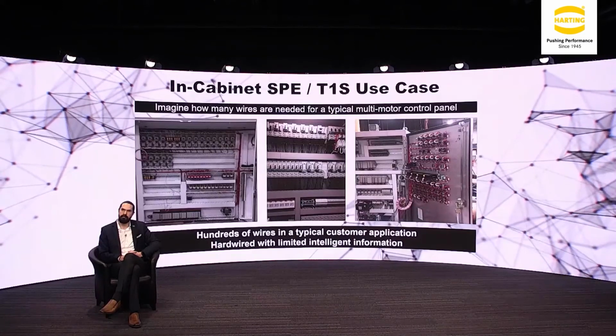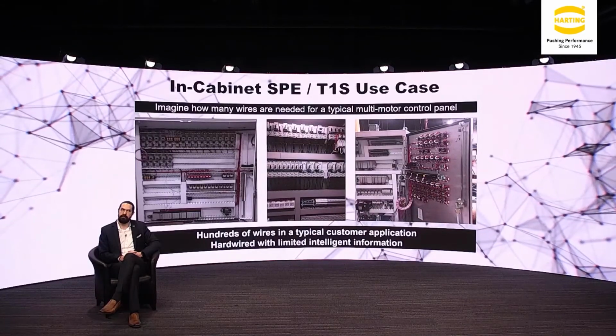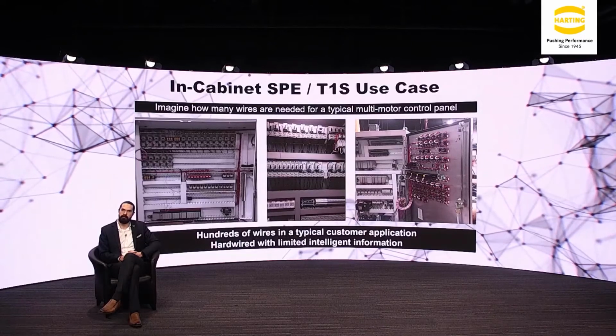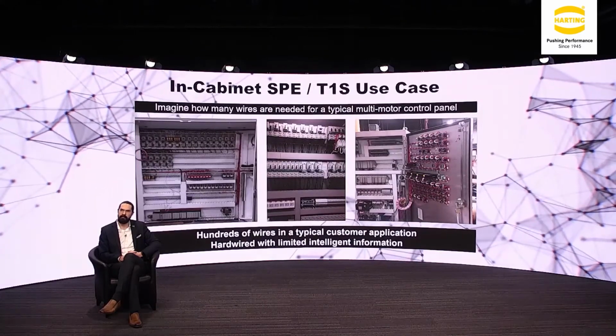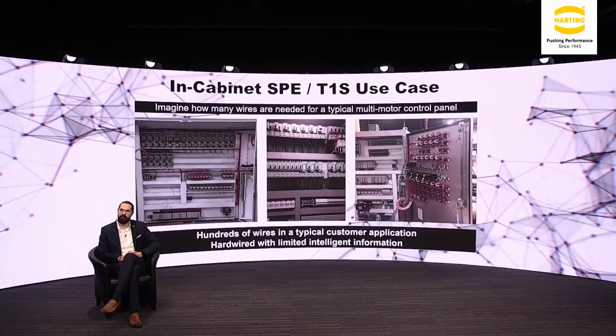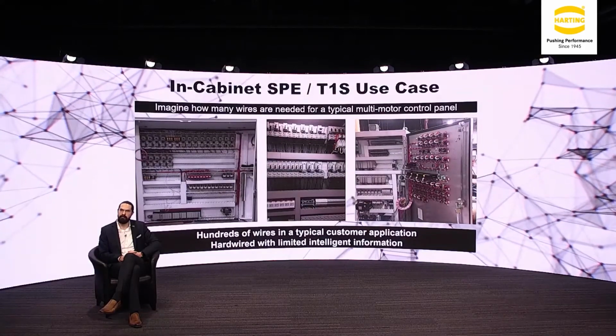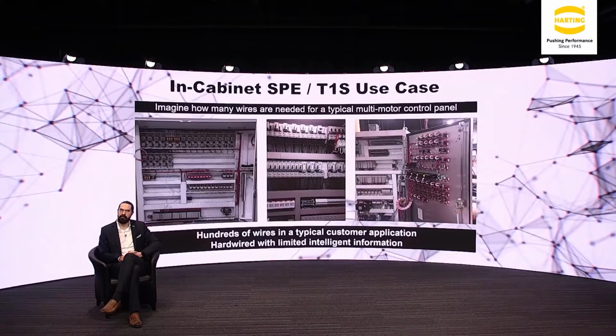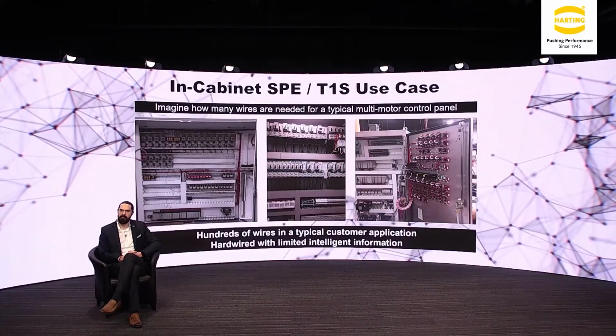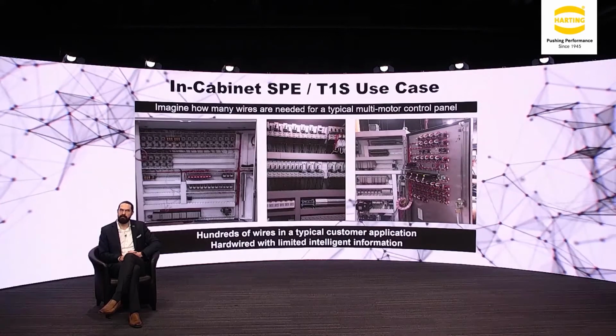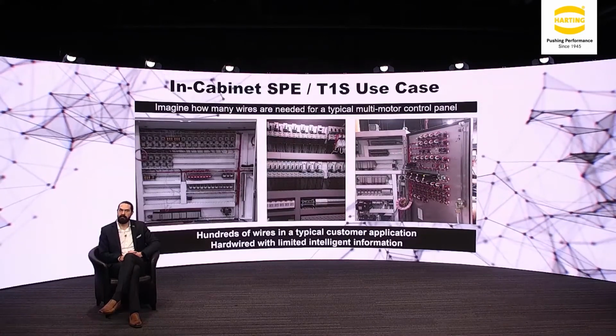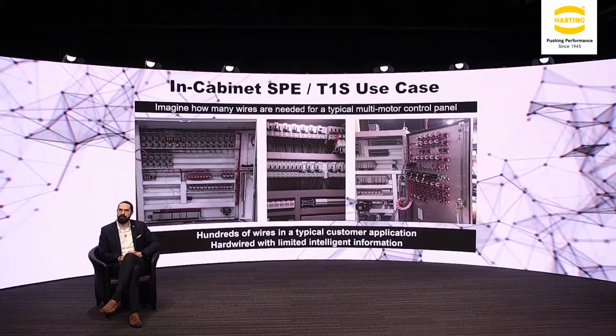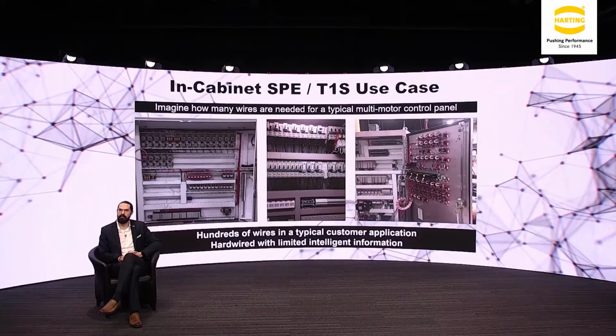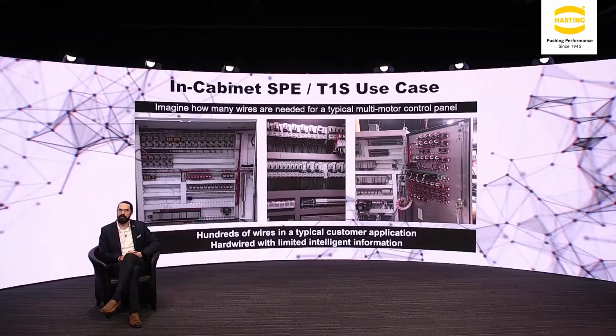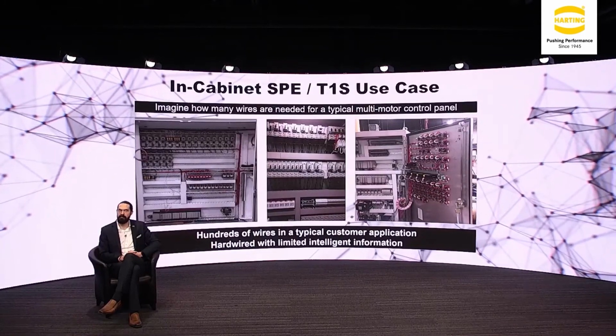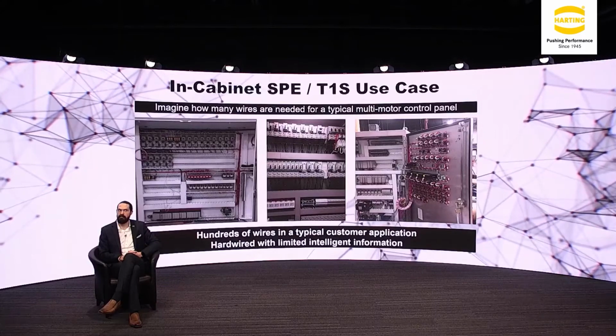Generally speaking, it takes a lot of effort to build a panel like this. There are tons of wires needed for a motor starter—for example, a unidirectional motor starter needs close to 8 or 13 wires to terminate from point A to point B. If you're controlling direction both ways, forward and reverse, you'd have up to 22 wires. Now imagine a panel with maybe a dozen motor starters, or even a hundred—you have thousands of wires. That's a lot of potential for miswiring.